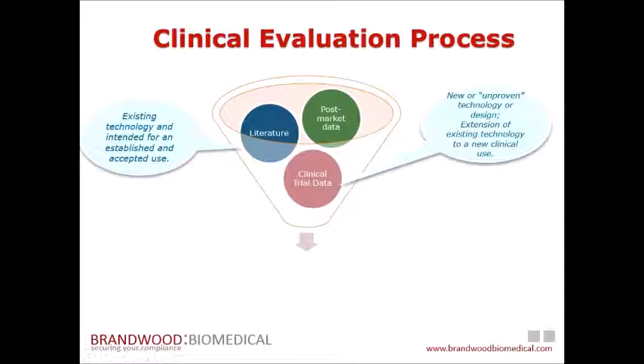And as guidance, normally clinical trial data is required if the technology or the device is new, novel, or unproven, and the design is basically novel, or if it's an existing technology but it has a new clinical use or a new clinical indication that currently is not found anywhere else in other devices. So in these cases, you would typically be expected to present direct clinical trial data. If, however, the device is based on an existing technology or the intended use is established and it has accepted use, then you can take the other pathway, which is the literature, drawing all the data from literature to provide the support for your device.